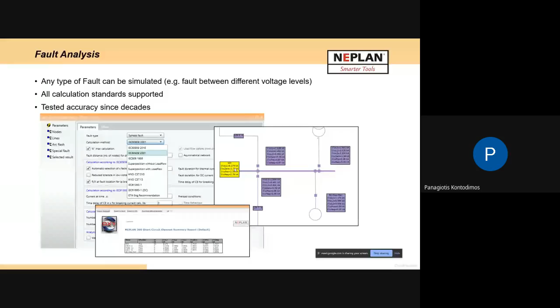Fault analysis is a very old and mature calculation. We can make all kinds of faults - 3-phase, single-phase, 2-phase - with several calculation methods, like the IEC and ANSI superposition methods, and we can see the results directly on the faulted location, or using reports and so on.